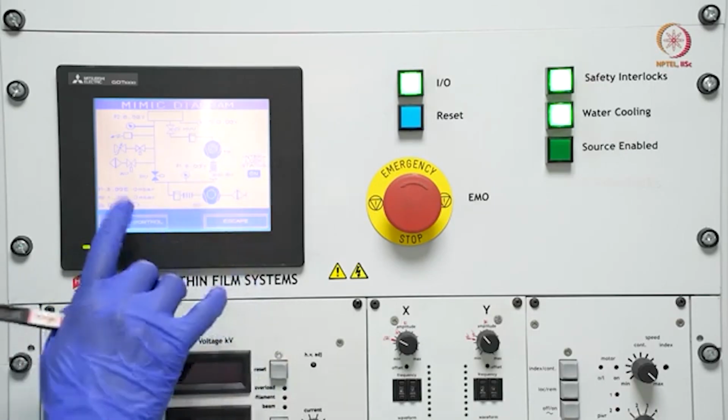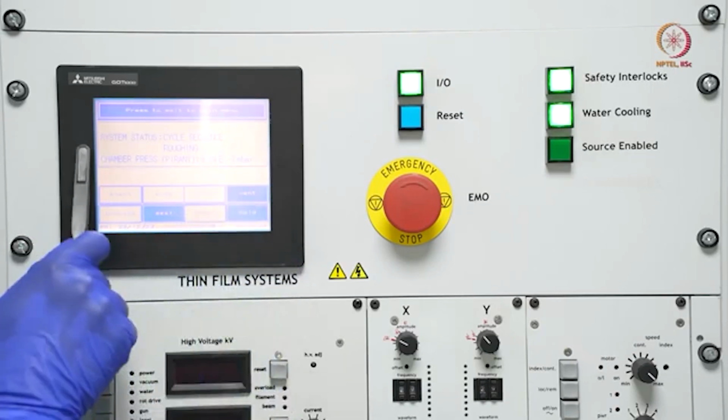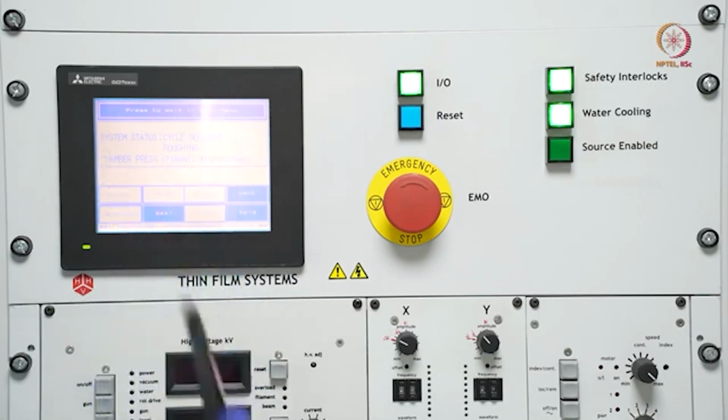So we will be there now. So okay, here you can see it is e power minus 1. We will wait till it goes to the high vacuum, or the high vacuum valve opens, and it goes for fine pumping using the turbomolecular pump through the backing line. Till that much we will wait, we will show in video. After that we will again come back when it reaches e power -6 pressure. So let us wait for that much time, a few minutes maybe, it will come.